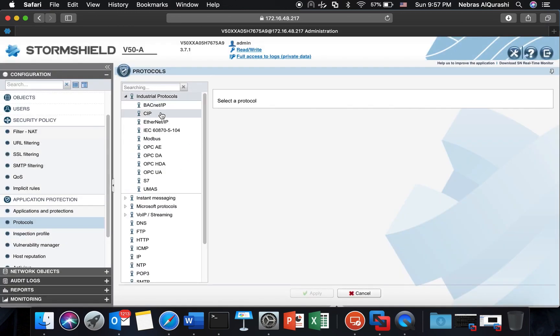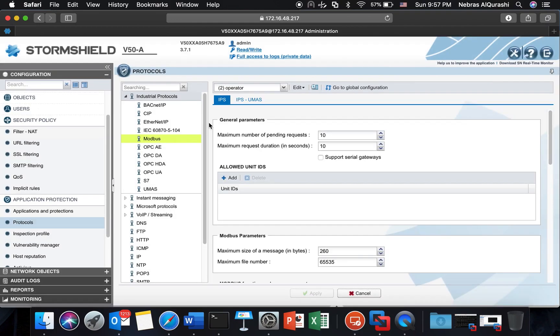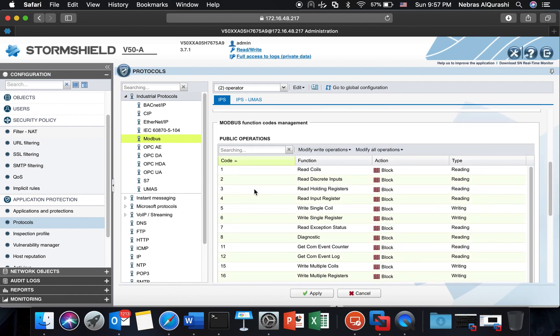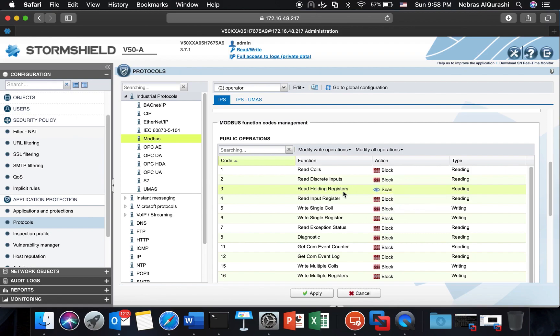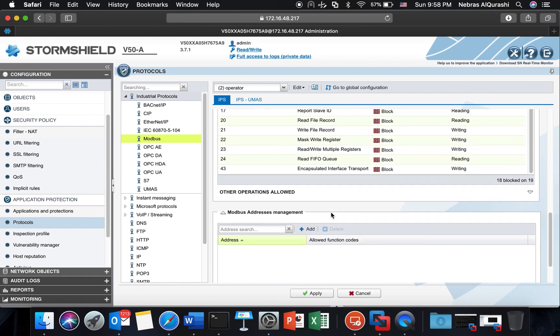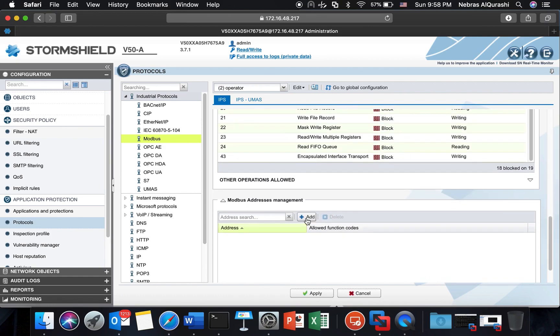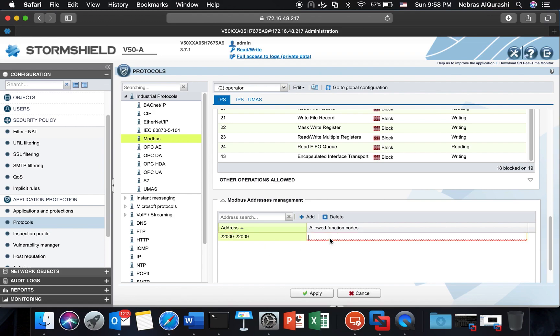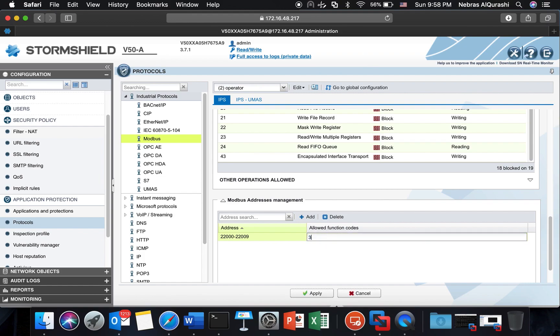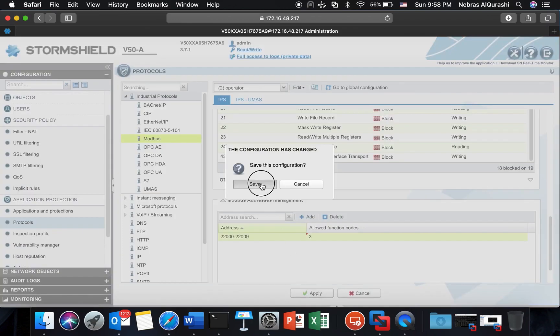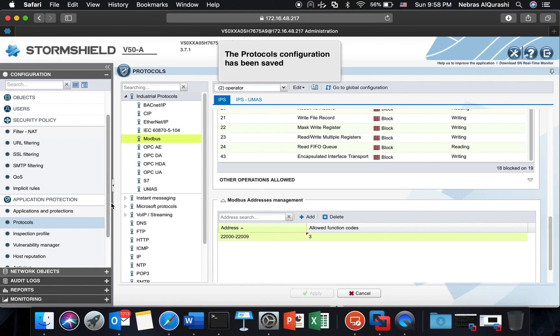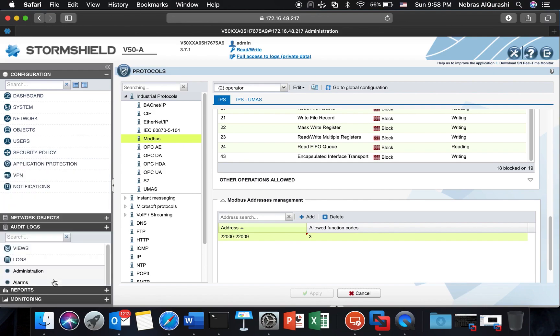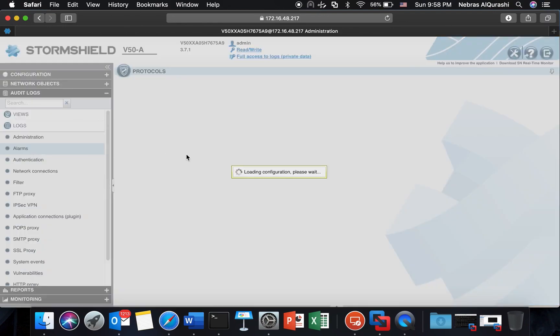I'm going to Modbus. The first thing I will add is the unit ID 99. Then I have the function code 3 so I will set it to pass, in fact we call it scan because we are still checking the protocol compliance. And then I add the address management. I have for the address from 22000 to 22009, and the function code is 3. Of course if I have more I could type comma 4 for example so I'm allowing 3 or 4. Apply and save.